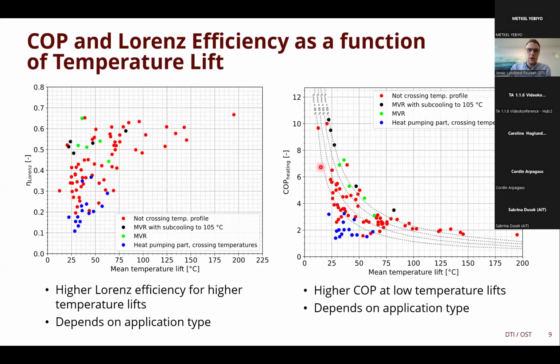If we look at the figure on the right-hand side, we have plotted all the stated COP against the mean temperature lift. An important general aspect to note, especially for those newer to heat pumps, is that even with a very efficient heat pump, where we have a Lorenz efficiency around 60%, there is a limit to how high a COP we can expect. We can see this curve when approaching temperature lifts above 100 degrees Celsius: it's not possible to have a COP higher than 2.